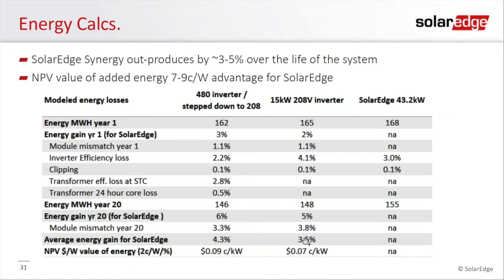And now the question is, what is the value of that extra production? Using a net present value calculation, this is a very common number that we see across the country. For every 1% increase in energy, the net present value of that extra revenue stream of electricity, not even taking into account SRECs or other environmental benefits you may have in your state, is about 2 cents. So that 4.3% of additional energy is worth about 9 cents a watt of extra value versus the 480, and about 7 cents a watt of extra value versus the 208 inverter.